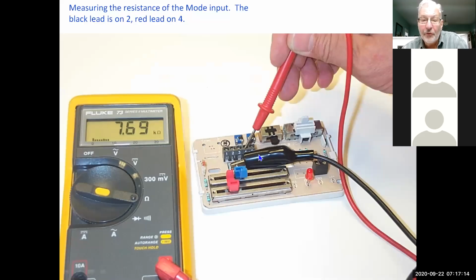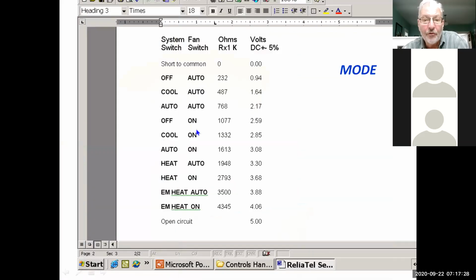You can also measure the resistance to see if the control's working fine. So if I go between terminal 2 and 4 and I'm reading 7.69 k ohms, and I go to this chart, it's telling me the system should be in the auto position, and the fan switch should be in the auto position. So every one of these, again, has a resistance value that corresponds to the control. And you can troubleshoot the control or the system by using ohms or volts to diagnose it.